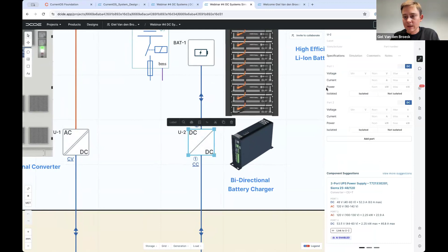current mode, I will configure that into constant voltage mode and also set it to 700 volt DC. As soon as you do that, you'll notice that the validation tab warns you that this won't work. Why this won't work? Because there are now effectively two voltage sources fighting each other in order to maintain that 700 volt DC level. That's one of the reasons why Droop control was invented many years ago, actually.